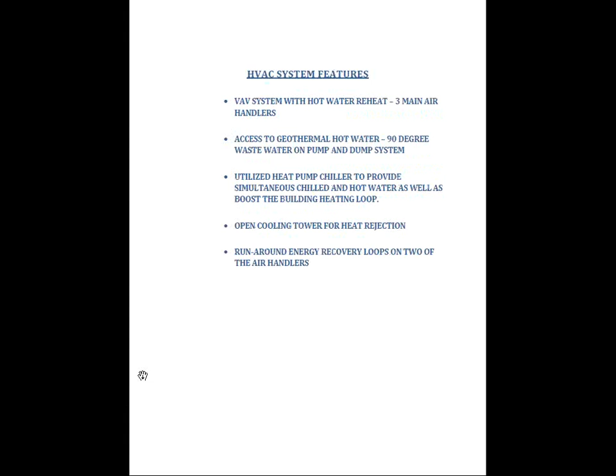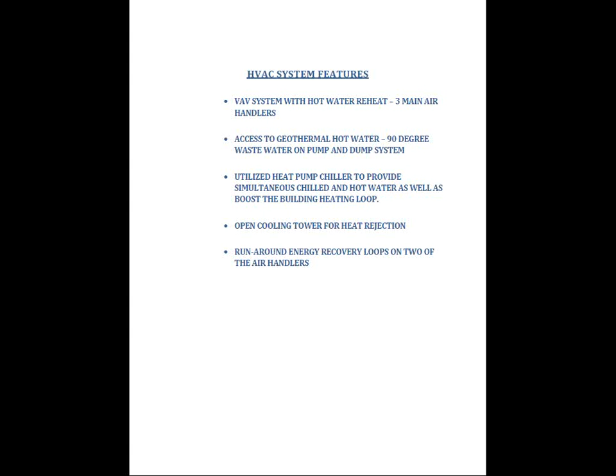Just to touch on the loops, to describe the HVAC system: the condenser loop is kept, I believe, at 70 to 80 degrees year round. Summer or winter time, it's more like 70 degrees. We have 90-degree wastewater, and the cooling tower is 80, 85, 90, 95. But that condenser loop is kept at 70 to 80 degrees, and then the heat pump produces 45 to 55-degree chilled water, and I believe it's 95 to 105-degree hot water out to the building.